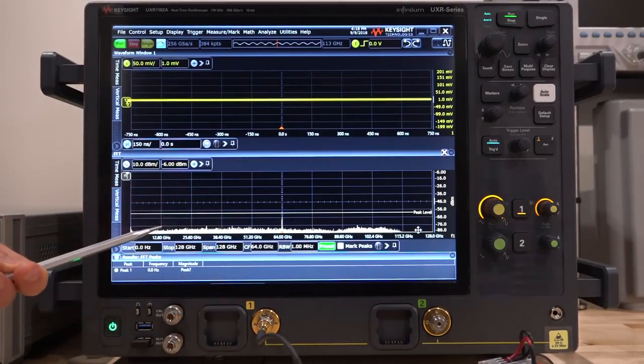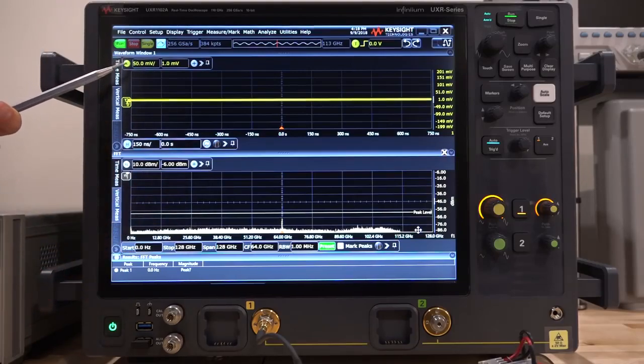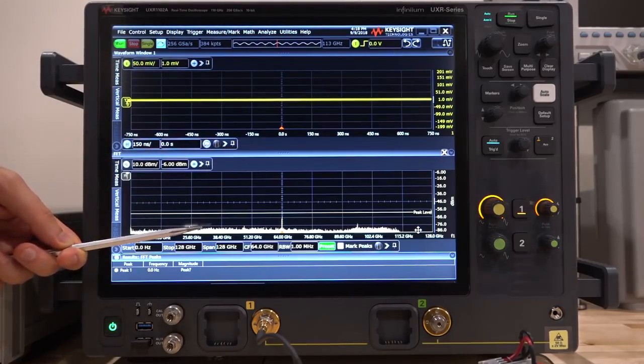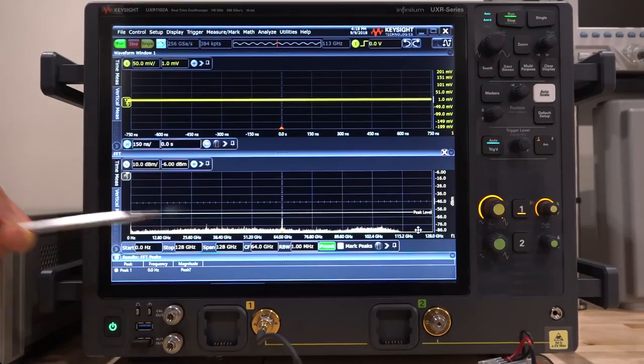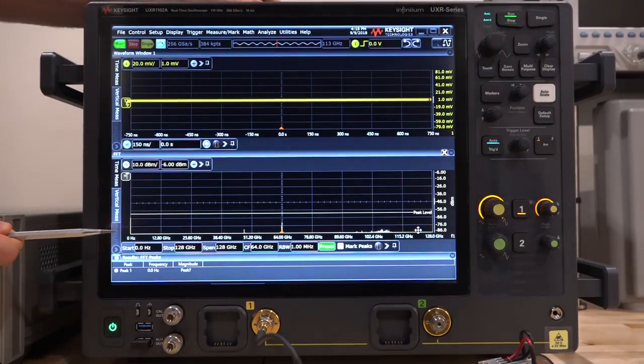So having said that, this is not even at the highest sensitivity, because we are at 50 millivolts per division. If I were to reduce this all the way down to 2 millivolts per division, the displayed average noise floor at the same settings is going to continue to get better and better. For instance, I can go down to 20 millivolts per division, and you can see that the noise is already much lower, even though the resolution bandwidth is exactly the same as it was before. So if you need to make a very sensitive measurement, you can get noise floor much better than minus 86 dBm, simply because you can go all the way down to 2 millivolts per division, which is the limit of the hardware front-end sensitivity. Now, of course, it means that the larger signal you can capture is going to shrink as well, but if you need to make sensitive measurements, that's the way to do it. So let's go back to where we were.